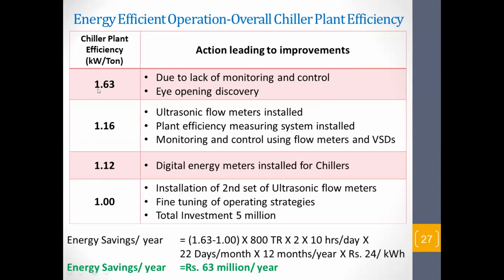What have they done? They have just replaced some of their instrumentation. The condenser water and chilled water flow meters were not working, and they didn't have power analyzers. At the time of construction of this building, power analyzers were a bit of a luxury. But now power analyzers are quite cheap. For 10,000-15,000 rupees, you can buy a power analyzer.